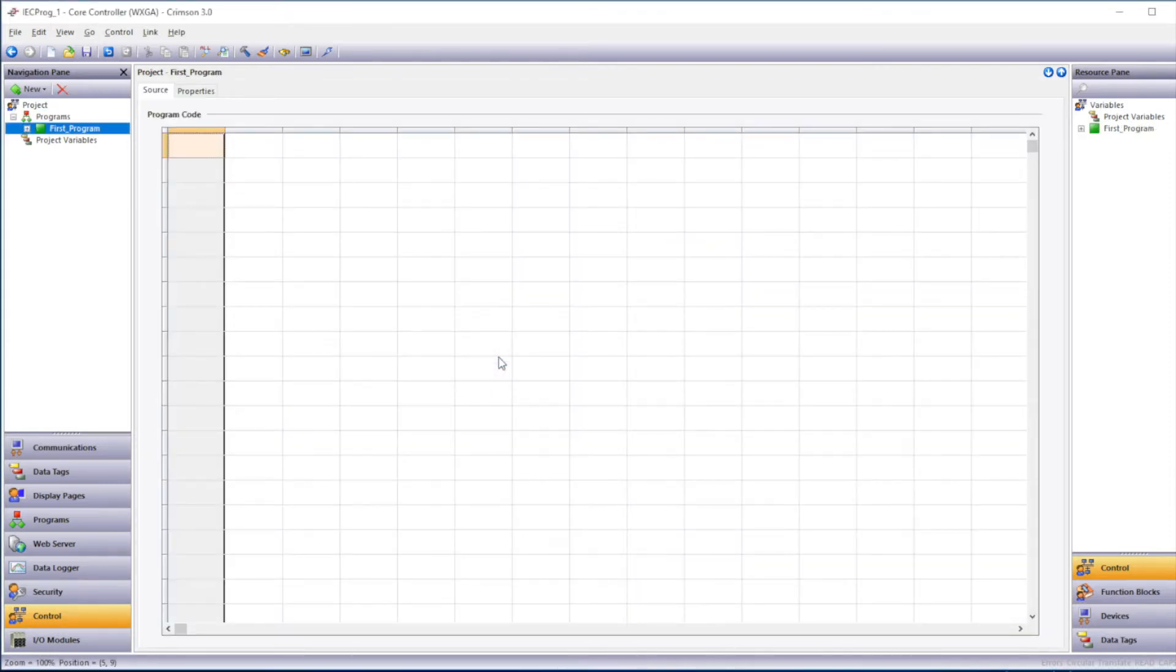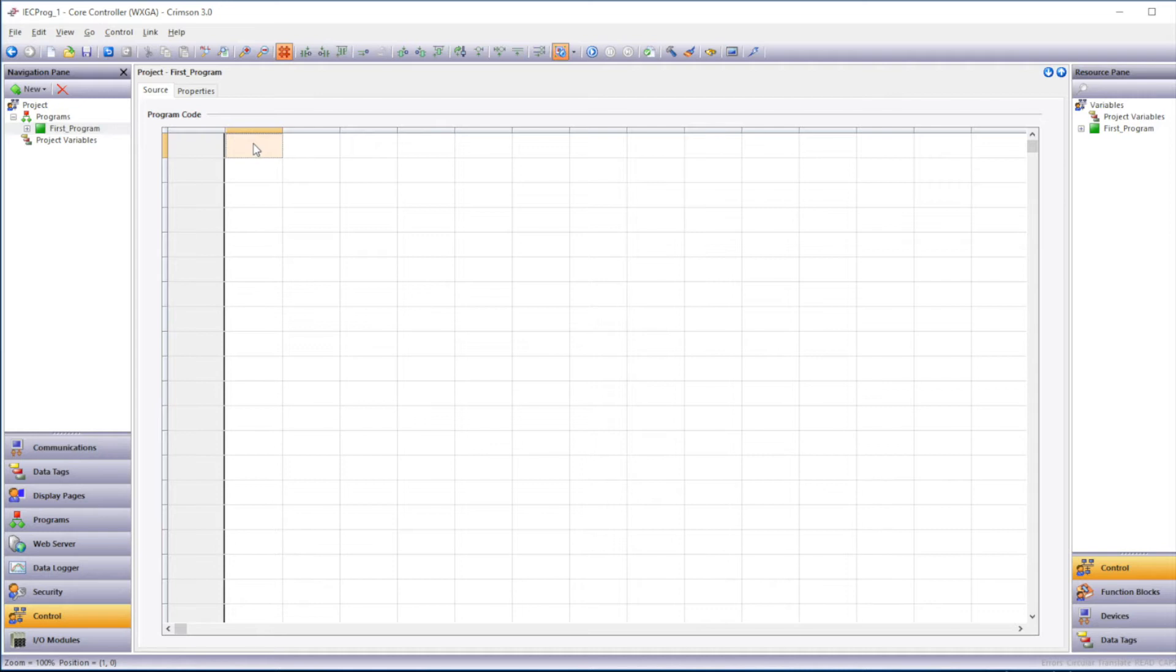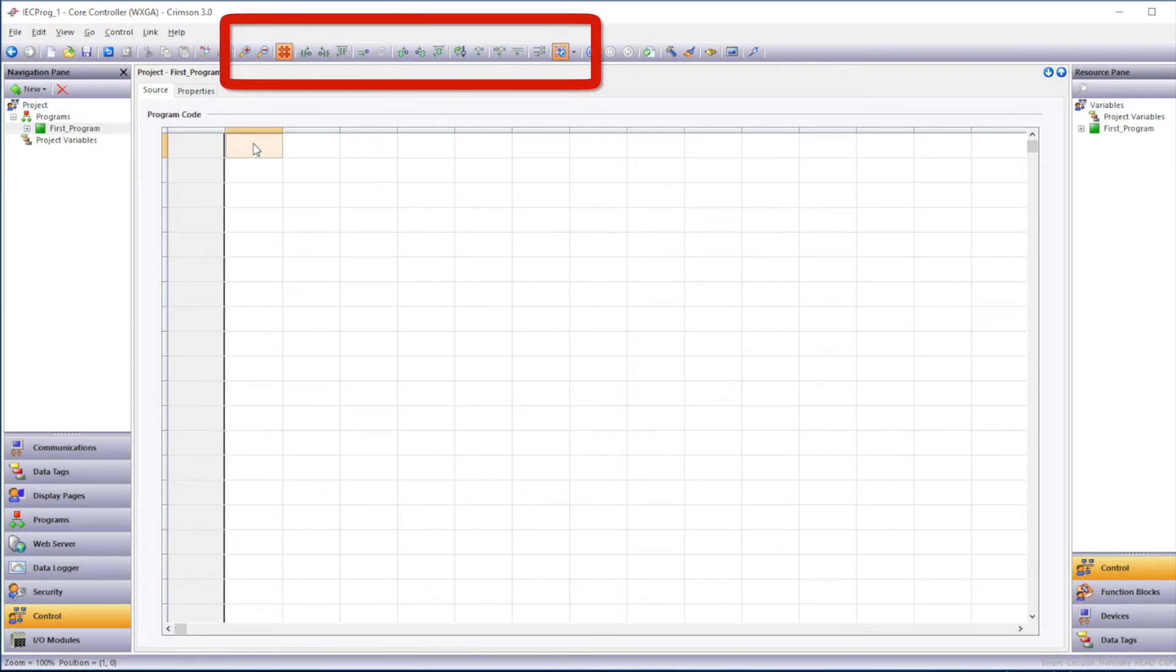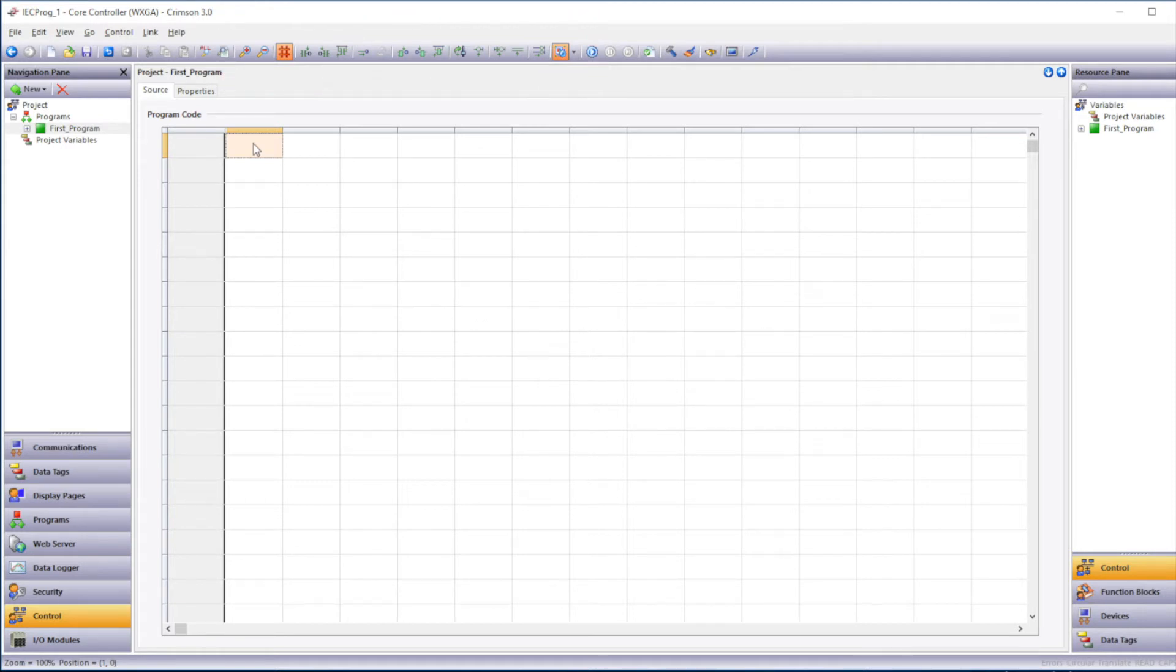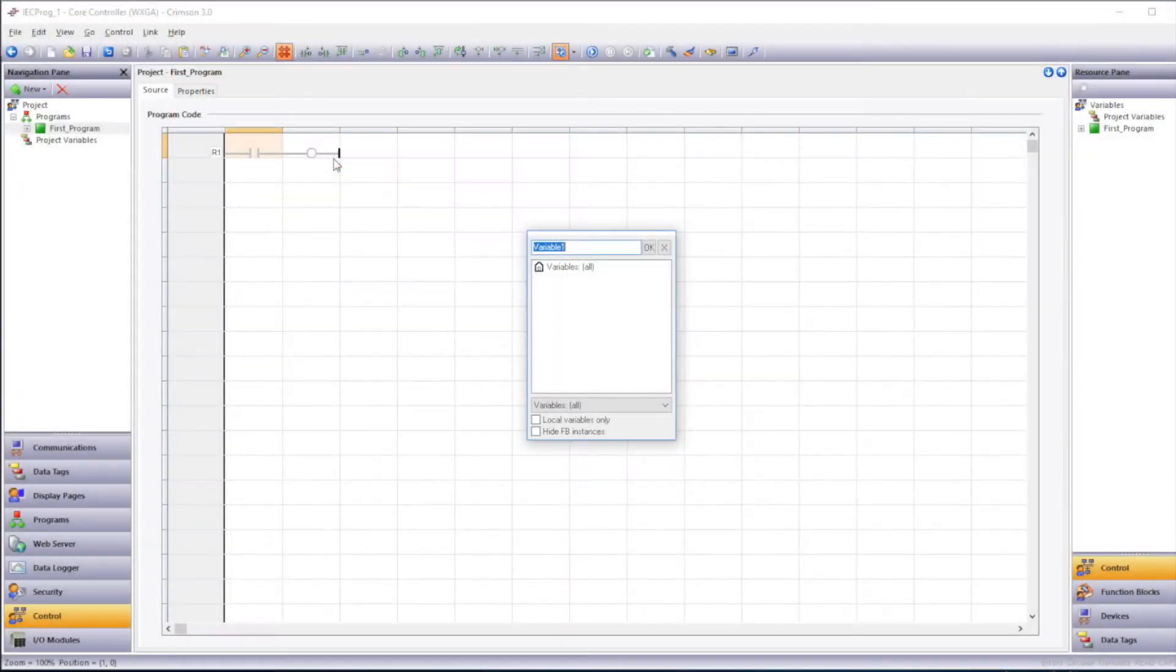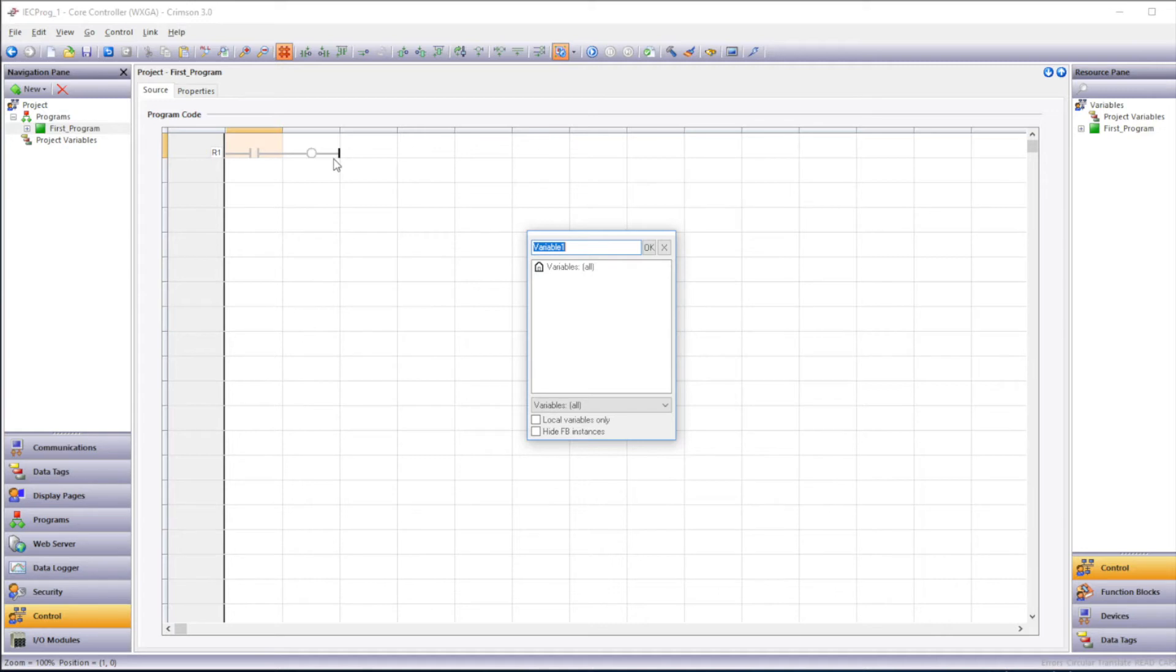The program we're creating will have an AND function with two switches and an output. But the idea is so when the two switches turn on, the output will turn on. Click in the Editor window. And you'll notice once you do that, the Editor toolbar will appear on the top of the screen. To insert a new rung, we'll start with a Contact. So we'll click on the Insert Contact Before or After buttons on the toolbar. And this will start off by creating our switch and a coil. And immediately what you'll see is that it will present us with a variable selection window, so that we can define which variable will be assigned to this contact.